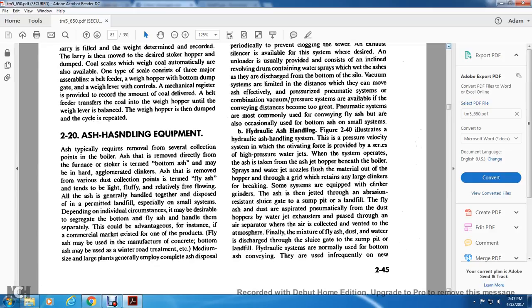Hydraulic ash handling. Figure 240 illustrates hydraulic ash handling with a pressure velocity system, in which the conveying force is provided by a series of high-pressure water jets. When the system operates, the ash dump hopper beneath the boiler sprays water jets to flush the material out of the hopper, through a grid which retains any large clinkers for breaking. Some systems are equipped with clinker grinders.